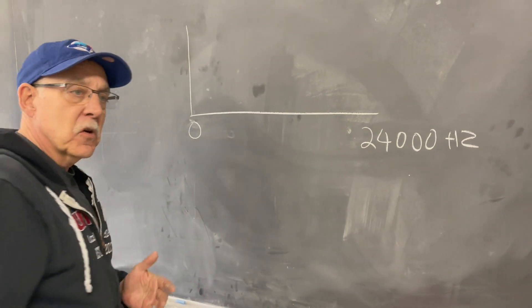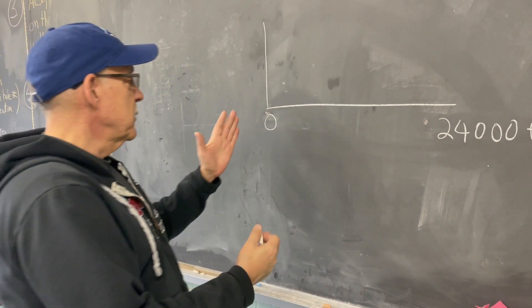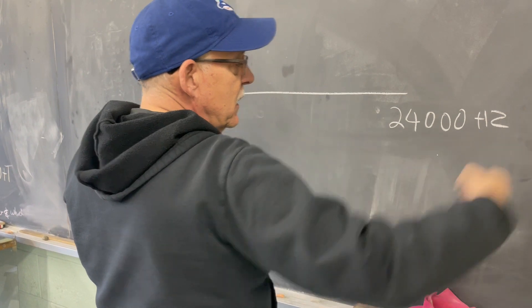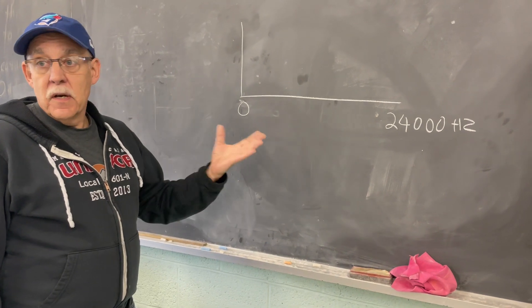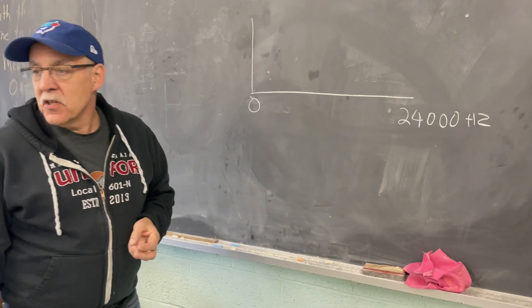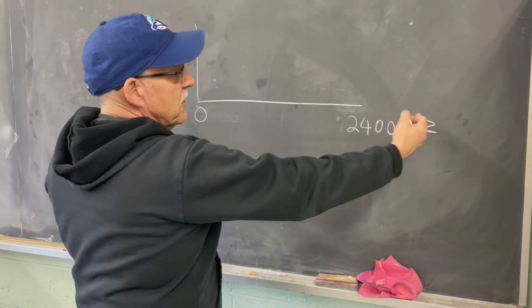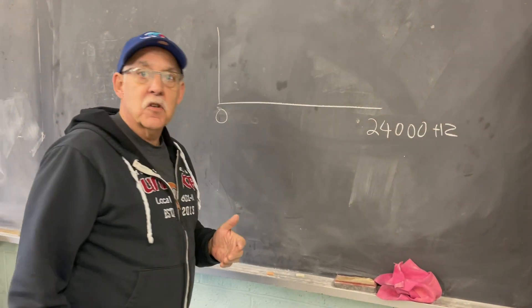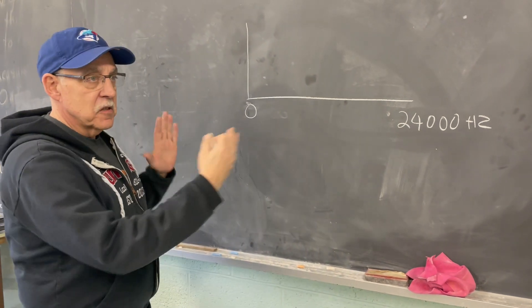How do we decide what the F-min and F-max should be? Whatever faults we want to zero in on dictates how we set up the window. If we want to look at all the information in the spectrum, we go from zero out to whatever we need. Generally, we take the primary frequency of the fault we're looking at and multiply by three. So if a gear mesh frequency was 10,000 hertz, we'd set the window at 30,000 hertz — just enough to see three harmonics of that primary frequency.